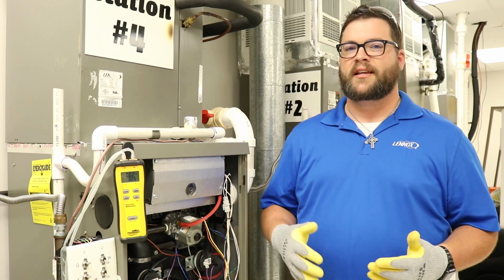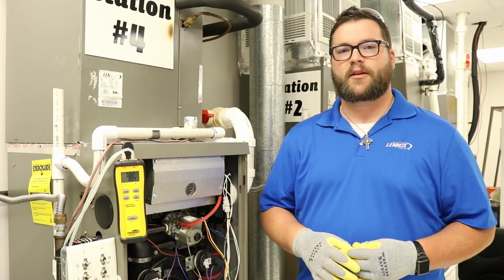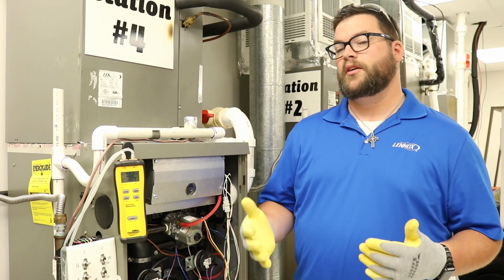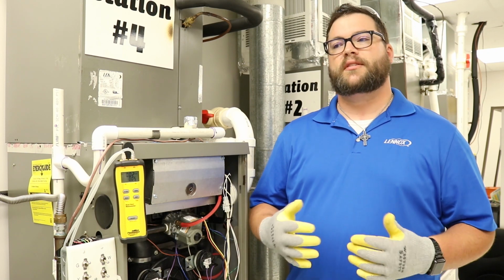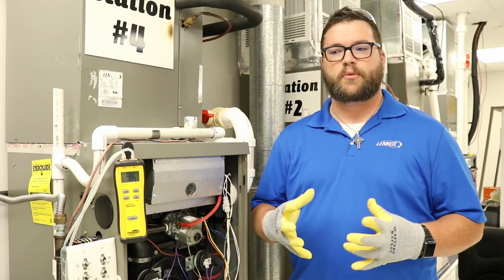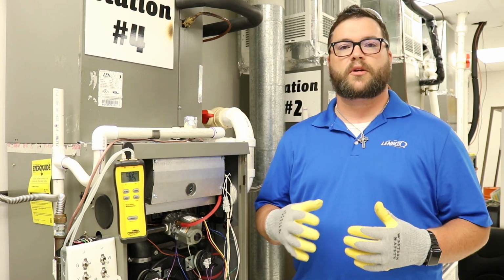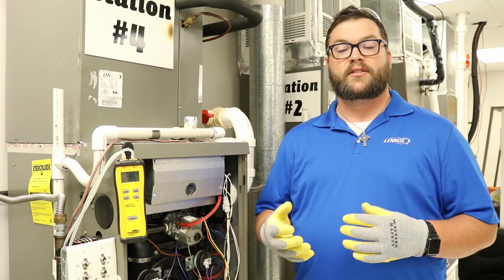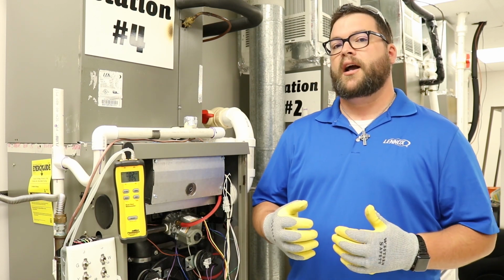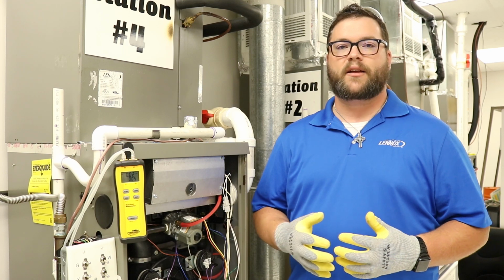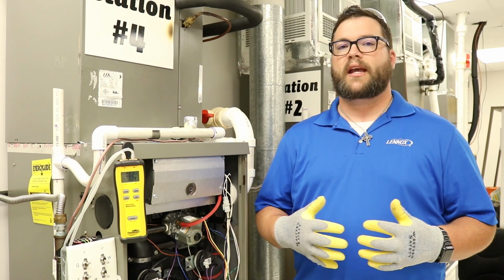And that question is, how do you properly check the static pressure on a system? And what good does that do you? So static pressure obviously is the pressure exerted on the ductwork throughout the system. And it is necessary to understand the parameters of that static pressure to be able to alleviate all kinds of issues.